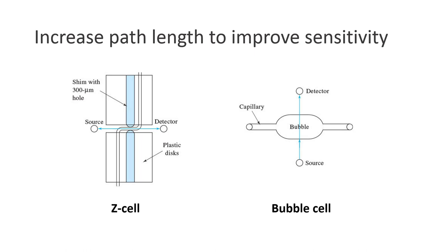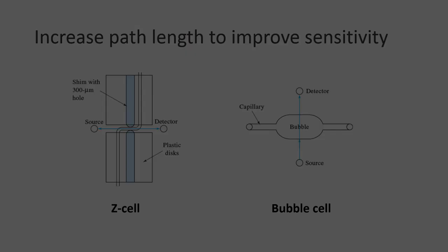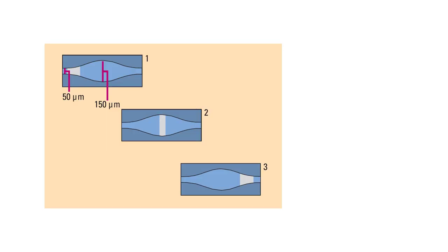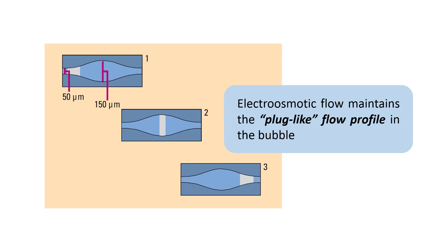Another approach is to use a bubble cell, which can improve the sensitivity by 3 to 5 times as compared to standard capillary. If the bubble cell is well designed, the electroosmotic flow is able to maintain the flat flow profile in the bubble so that the resolution would not be compromised.